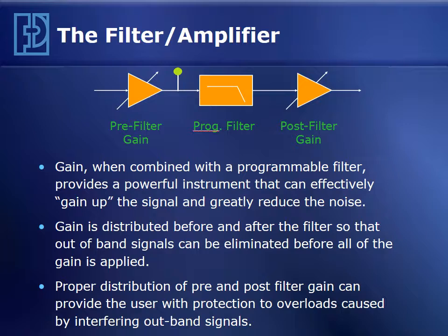The filter will mask an overload condition at its input. The output of the filter may look like a perfectly reasonable signal, but the input could be overloaded, and if you don't have an overload detector built in the amplifier, you would never know. So we always include a pre-filter overload detector with our instruments.